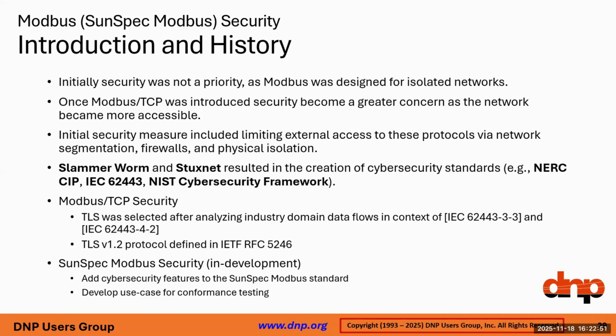To secure Modbus in the context of a network requires a lot of external devices - firewalls, network isolation, other controls in the network. Over the years, some very control-system-specific firewalls were developed. Even Cisco and some of their firewalls and intrusion detection systems have very specific Modbus carve-outs where you can get very granular restrictions of Modbus commands, but there's really nothing inherent to the protocol itself.